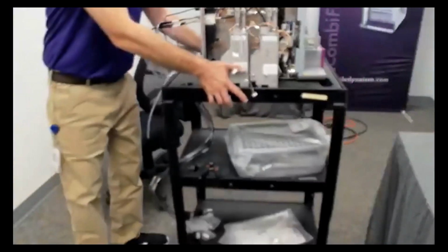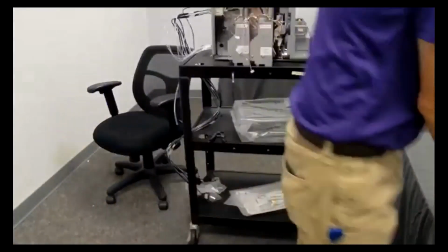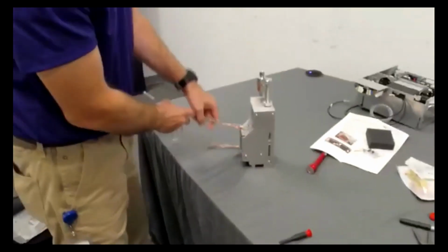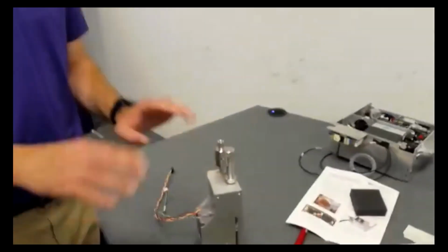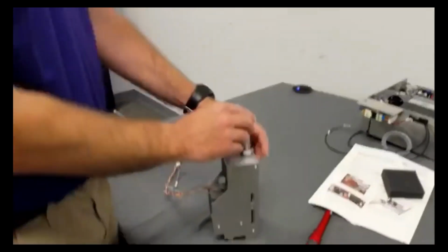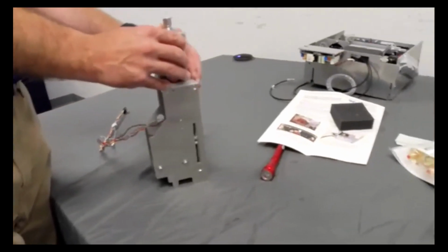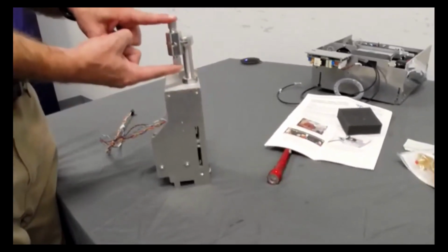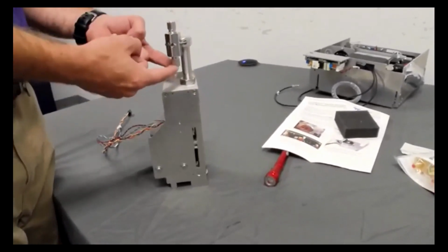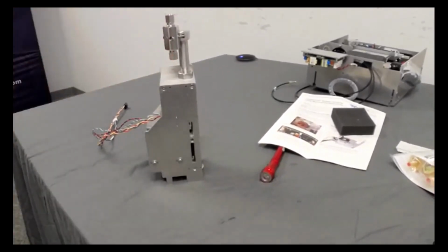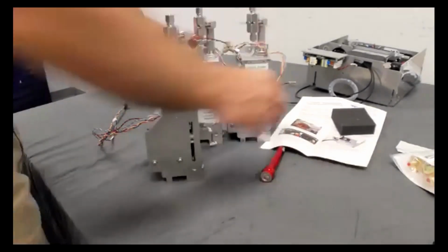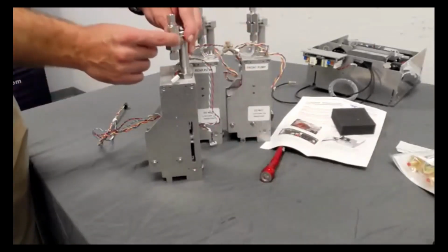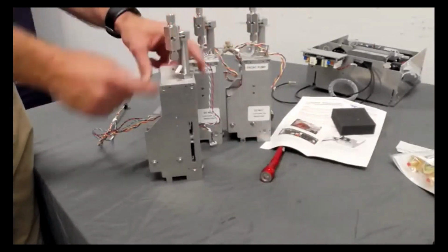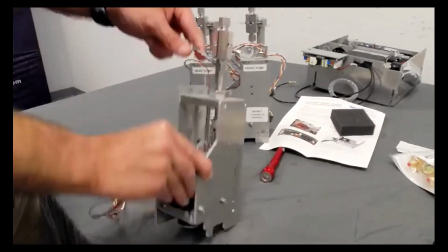So we're gonna move that out of the way. And I'm gonna work on my example pump here. So imagine that I just took this out of that unit. Let's pretend. Now, the first thing you're gonna see is you've got your check valve housing. You may have that tubing line on the underneath still, like what we had here, okay? It's fine to leave those on there, because what we're gonna do is we're gonna take this check valve housing off, okay? So in order to do that, you use your Allen head.